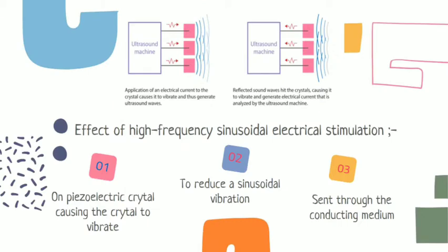So, for example, based on the picture, a piezoelectric crystal vibrates when an electric signal is applied, producing a high frequency sound pressure wave, which we call ultrasound. More importantly, this type of crystal can also work in reverse. It can produce an electrical signal when it detects a high frequency sound pressure wave. When a transducer sends ultrasound waves into the body, they pass right through the skin. As the waves encounter tissue with different characteristics and densities, they produce echoes that reflect back to the piezoelectric crystal, as shown in picture number 2.